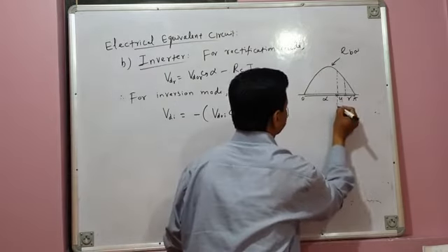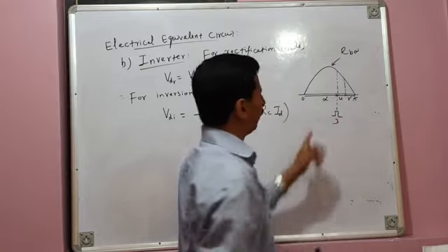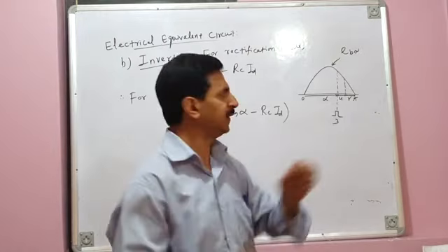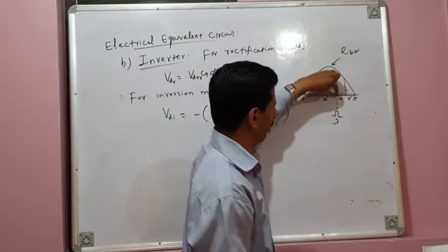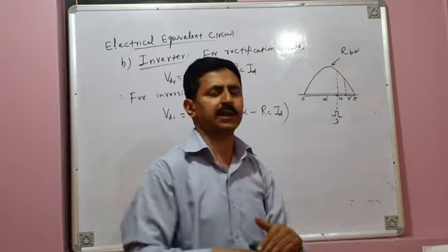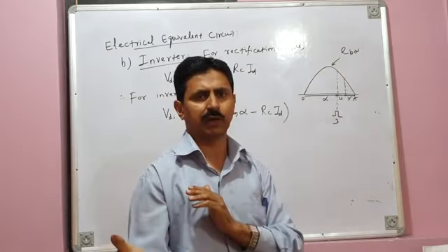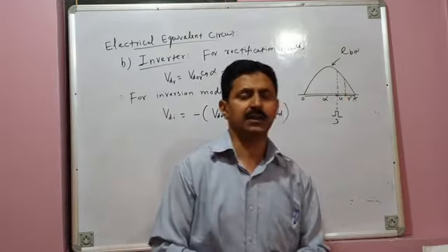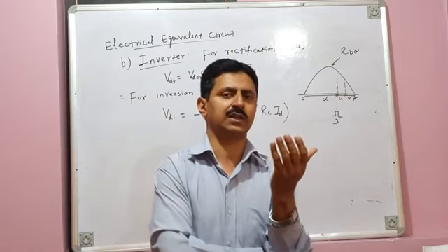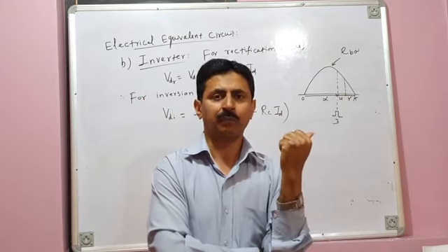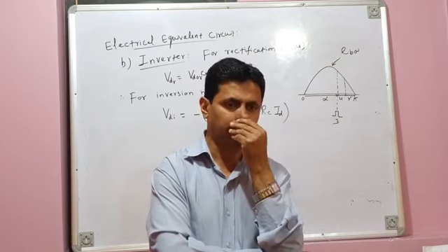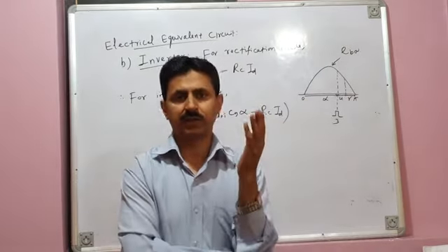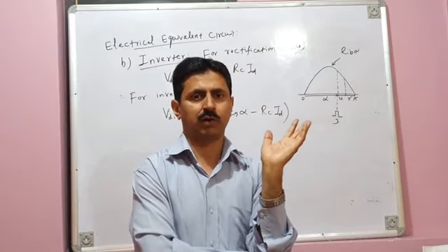Valve 3 is fired here. You fire valve 3 here. And 1, 2, 3 valves conduct. And there is commutation between 1 and 3. And the valve 3 conduction occurs during this U. And once the commutation is over, then again you have 2 valve conduction. 1, 2, 3 will be followed by 2, 3. And this gamma is extinction angle. It is the time period during which reverse voltage is applied across outgoing valve 1. And I have already told you that for avoiding the commutation failure, this gamma should be 10 to 15 degrees. In one of the earlier lectures, I have already explained.